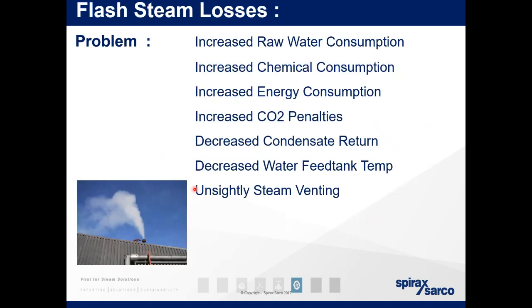So, flash steam losses, problems. Many of you will see this on your site. First, increased raw water consumption, because you're having to produce more steam. Increased chemical consumption, again because you're producing more steam. Increased energy consumption, like I said before, you're making more steam. Increased CO2 penalties. That's probably more for the European markets, but some of your industries will have to pay fines depending on how much CO2 you're producing. Decreased condensate return, so the temperature going back to your feed tank is lower and you're having to do more heating. Decreased feed water temperature, as that hot condensate isn't being returned.